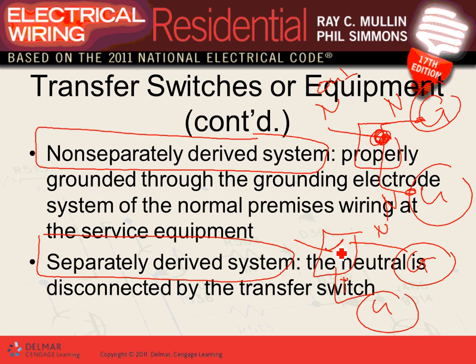Here, they're switched. Can you guys see that? So I switch the neutral. I can pick between the neutral coming from the generator or the neutral coming from the utility. That's called a separately derived system. If it's a separately derived system, they require you to take the neutral here, guys, and bond it to the ground. You bond the neutral to the ground at the generator for a separately derived system. For a non-separately derived system, you cannot bond the neutral to the ground at the generator level, so the generator will be grounded, but not the neutral.